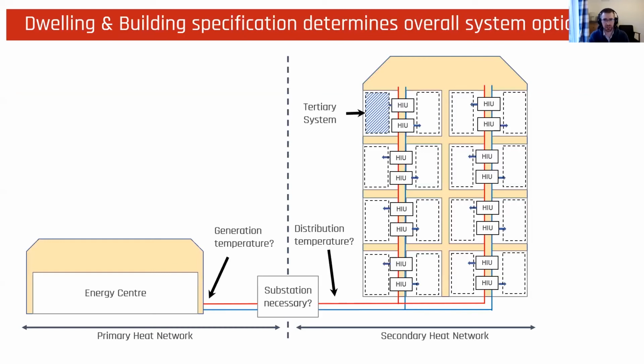So in terms of minimising distribution temperatures, we've heard a little bit about this already, but it's that thought process of, I'm not just going to jump straight to my energy centre design. I'm going to start a new build development by thinking about what temperatures I need to get to the end dwelling. So in the tertiary system, space heating, domestic hot water, what temperatures do I need to distribute at? Do I need substations? Are they actually necessary? Can I remove them? Because every time I have one, I have to have those jump up in temperatures, so that I then get back to what generation temperature my energy centre needs to produce, and is that suitable for the heat pump technology I've got in mind?